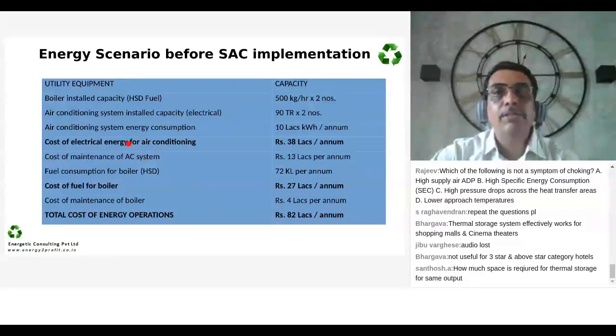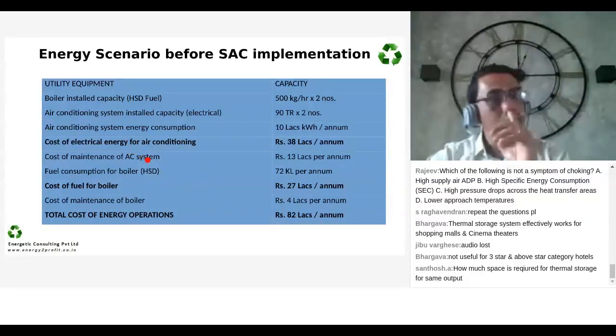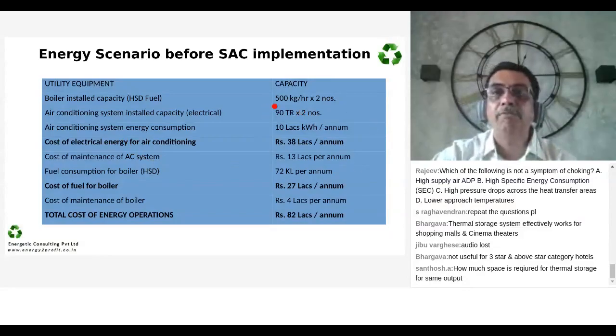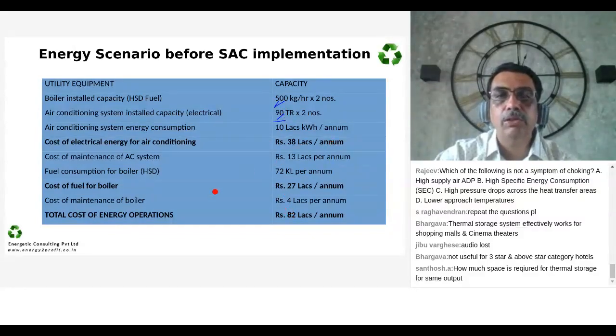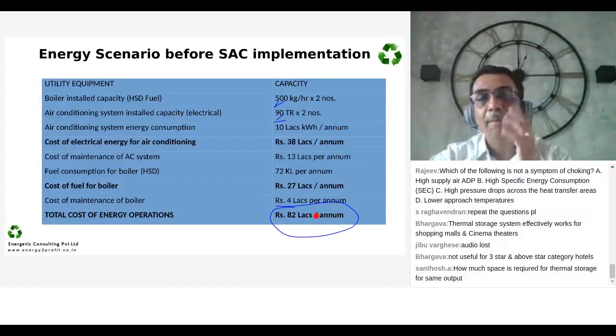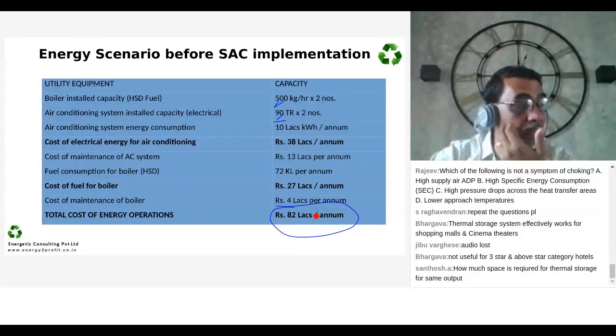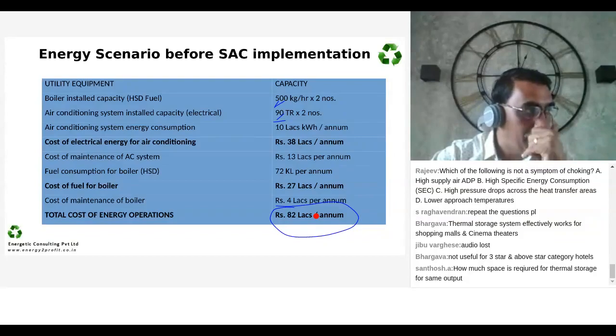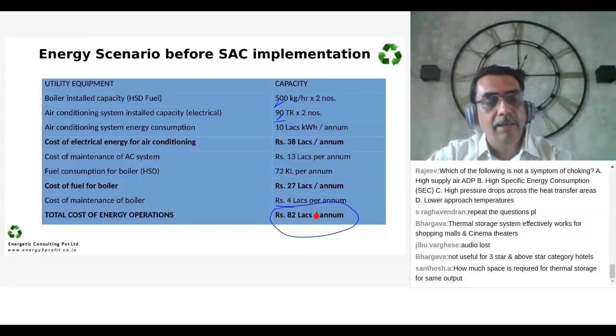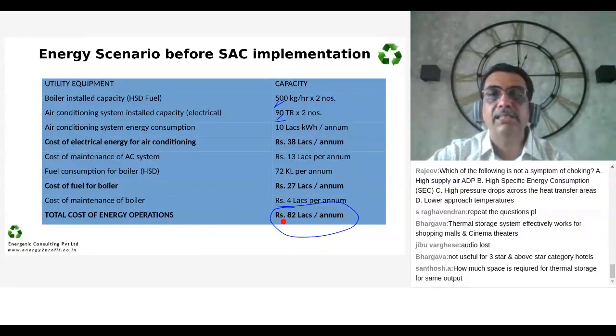Now, what was the system earlier? There were boilers working on diesel. There were air conditioning system chillers working on electricity, and the total cost of operation, including fuel, was around 82 lakhs per year. By the time this system got implemented, this 82 lakhs became 1.25 crore because there was a substantial increase in electrical energy cost and the fuel cost.